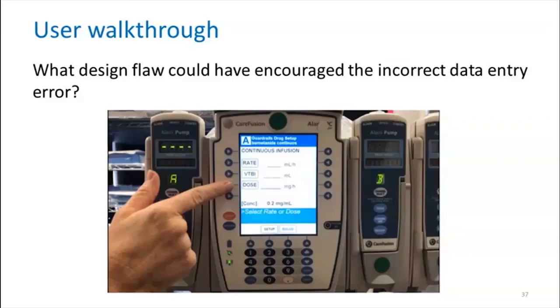From this walkthrough, what we should note is that the design of the pump's interface doesn't match the way the nurse enters the data. Specifically, a nurse starts by entering the dose, which, as you can see, the dose field is the last one listed on the screen. The rate field, however, is the first field listed on the screen, and that's where our nurse accidentally entered the dose value. So the design flaw that contributed to this adverse event would be that the order of the fields does not match the user's data entry task.